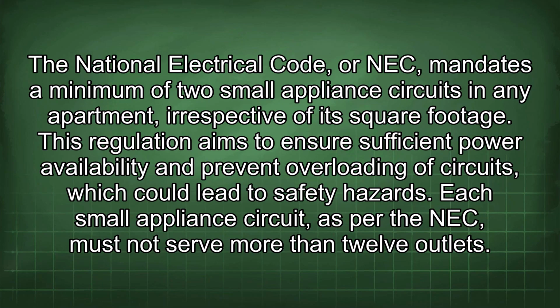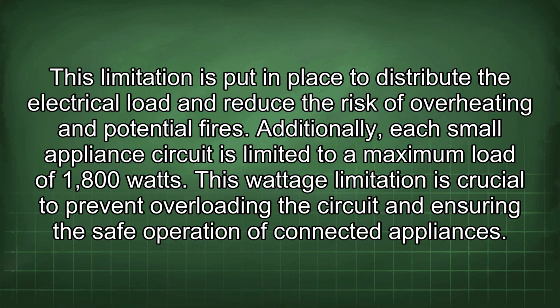The National Electrical Code, or NEC, mandates a minimum of 2 small appliance circuits in any apartment, irrespective of its square footage. This regulation aims to ensure sufficient power availability and prevent overloading of circuits, which could lead to safety hazards. Each small appliance circuit, as per the NEC, must not serve more than 12 outlets. This limitation is put in place to distribute the electrical load and reduce the risk of overheating and potential fires. Additionally, each small appliance circuit is limited to a maximum load of 1800 watts. This wattage limitation is crucial to prevent overloading the circuit and ensuring the safe operation of connected appliances.